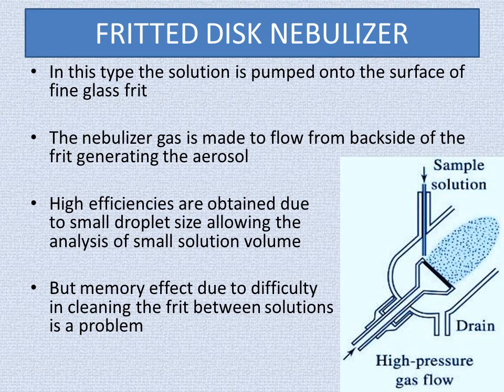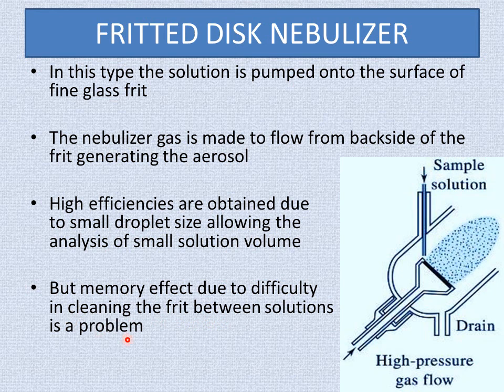Another design is the fritted disc nebulizer. In this type the solution is pumped onto the surface of a fine glass frit, and the nebulizer gas is made to flow from the back side of the frit, generating the aerosol under high pressure. High efficiencies are obtained due to small droplet size, allowing analysis of small solution volumes. However, a significant problem with this nebulizer is the memory effect, due to difficulty in cleaning the frit between solutions.